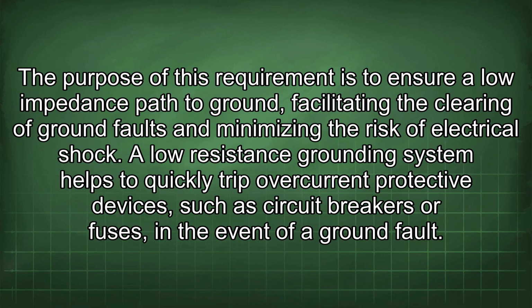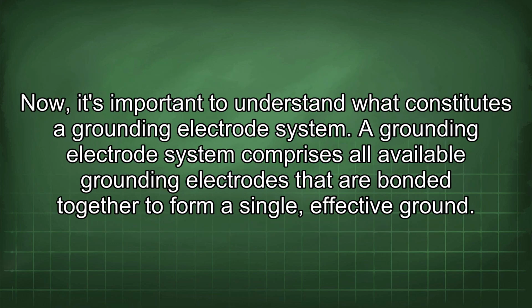A low resistance grounding system helps to quickly trip overcurrent protective devices, such as circuit breakers or fuses, in the event of a ground fault. Now, it's important to understand what constitutes a grounding electrode system. A grounding electrode system comprises all available grounding electrodes that are bonded together to form a single, effective ground.